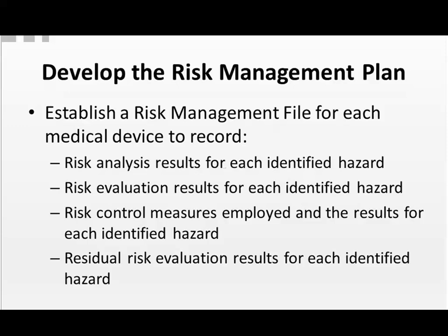Now, as I gave you a brief overview prior to this, we established this file to record the risk analysis results for each identified hazard, the risk evaluation results for each identified hazard, the risk control measures employed and the results for each identified hazard, and the residual risk evaluation results for each identified hazard.